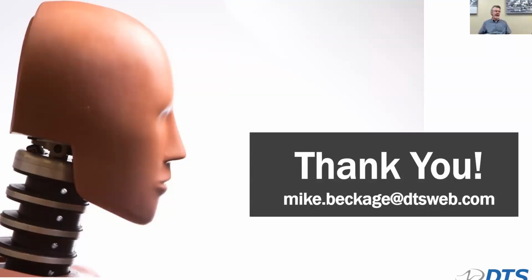Great question I can answer right off the top here. We had a question asking, will the older TDAS Pro support the new SAE J211? The answer is yes. Even though TDAS Pro was developed between 1997 and about 1999, it will absolutely support the new SAE J211. TDAS Pro modules have, for their entire lifetime, been able to sample all 8 channels at up to 38,000 samples per second per channel, and the filters meet all the requirements for any new J211. So yes, no sweat there.